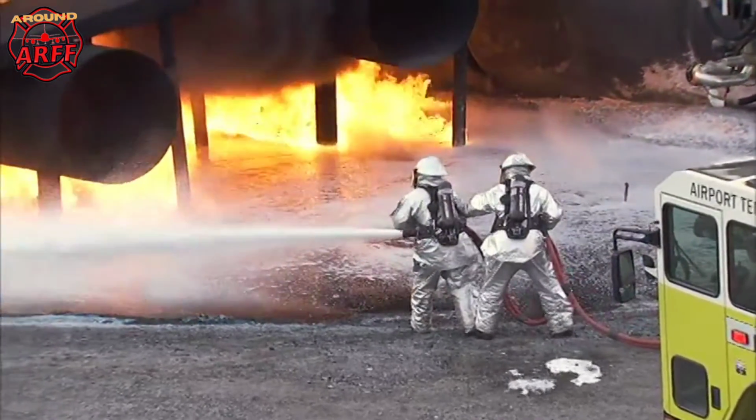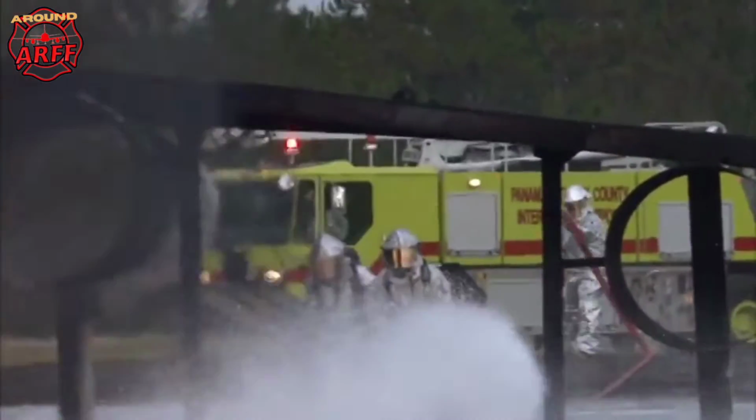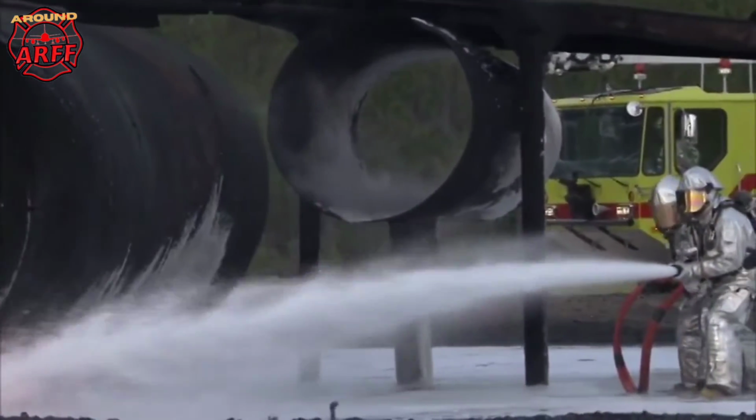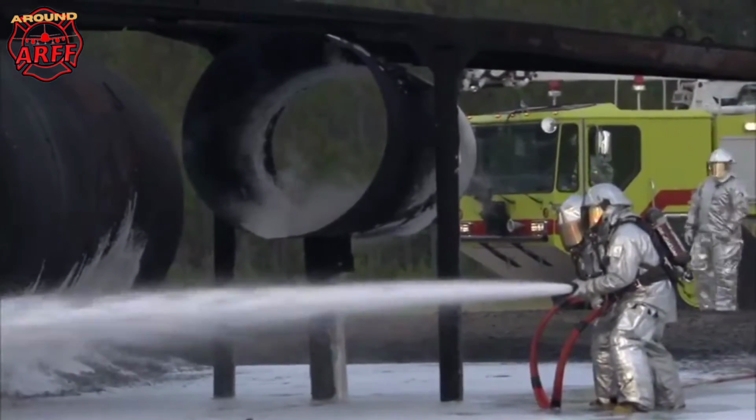positions along the edge of a liquid spill to cover the entire pool. Continue to apply foam until it spreads across the entire surface of the fuel and the fire is extinguished. Use the roll-on method only on pools of liquid fuel, ignited or unignited, on the ground or pavement.